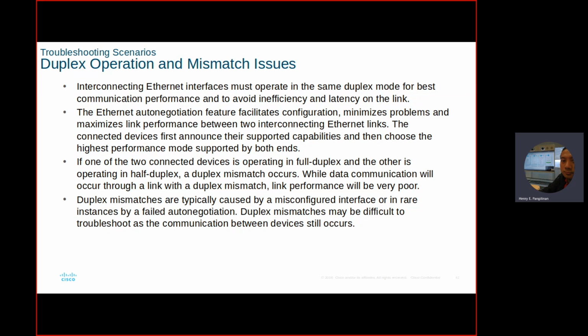If one of the two connected devices is operating in full duplex and the other is operating in half duplex, duplex mismatch occurs. While data communication will still occur through a link with a duplex mismatch, link performance will be very poor. So duplex mismatches are typically caused by misconfigured interfaces or, in rare instances, by failed auto negotiation. Duplex mismatches may be difficult to troubleshoot as communication between devices still occurs.